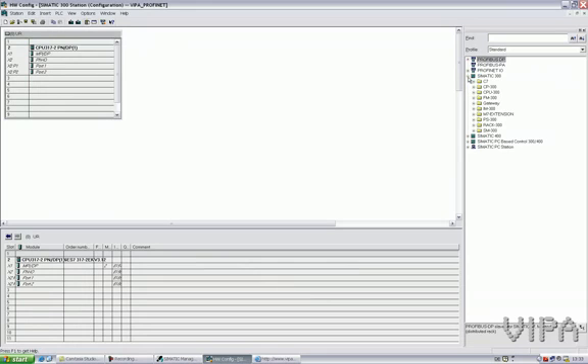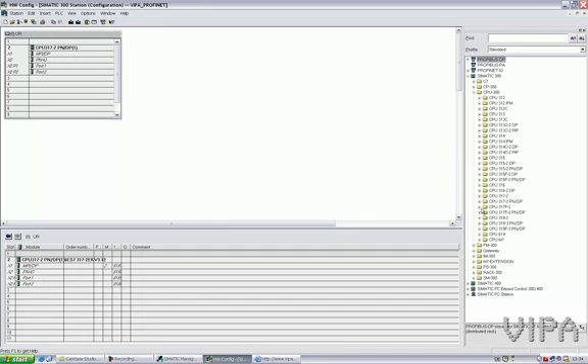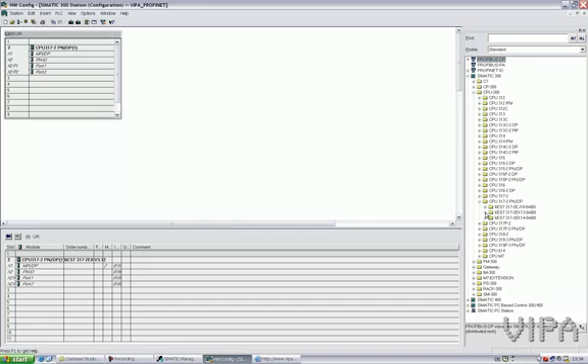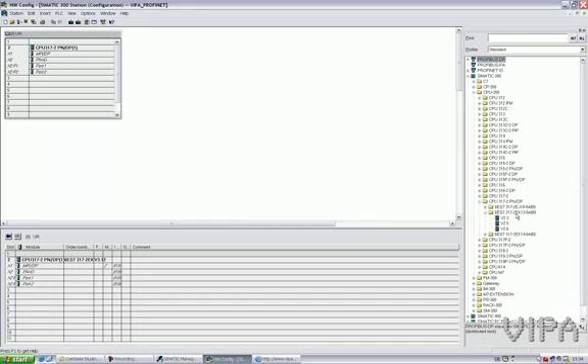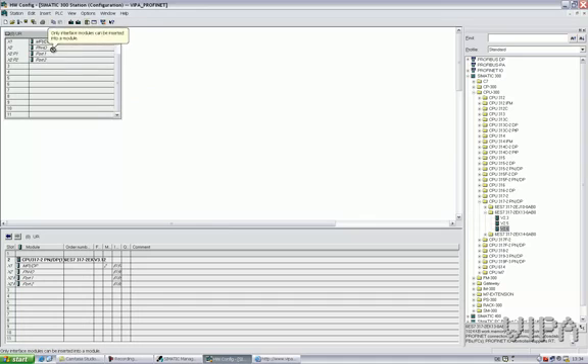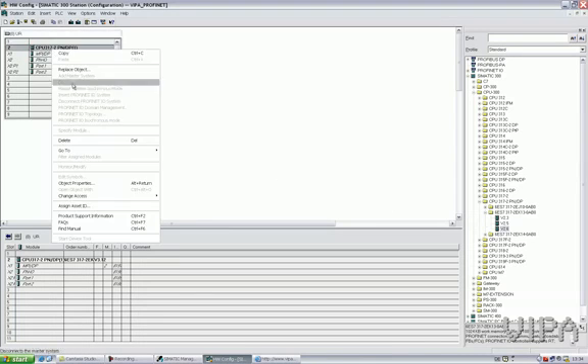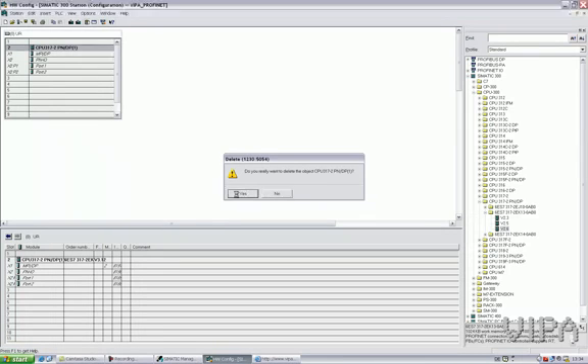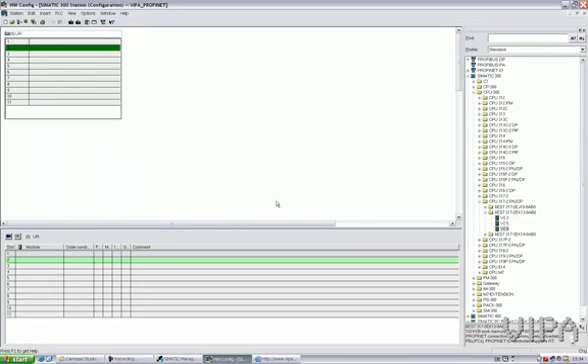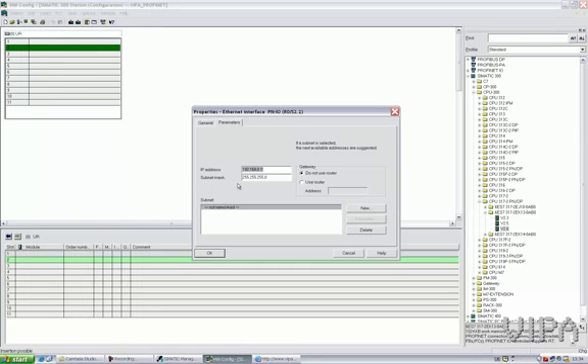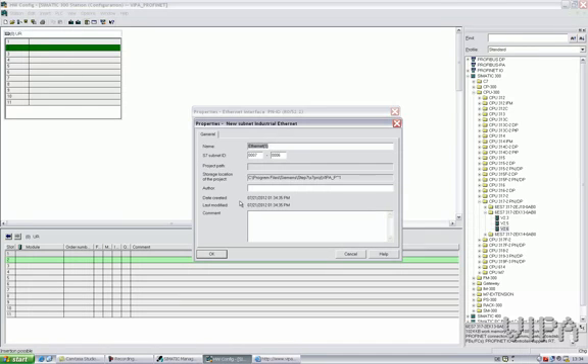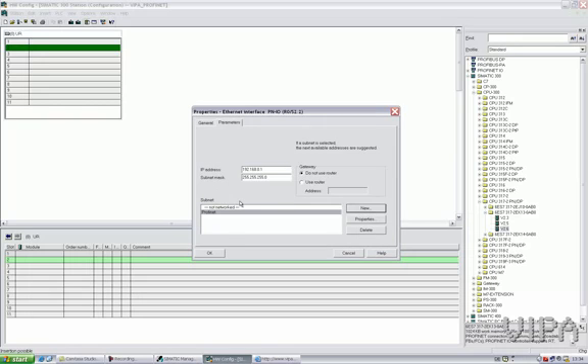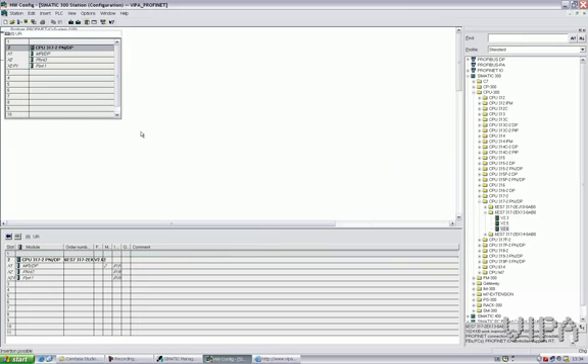So, in the hardware catalog of Simatic Manager, I go to the CPU 317 PN-2EK13 version 2.6. Okay, I'll first delete this one. Delete. Yes. And no, I do not want to delete my OB1. IP address is fine for me, 192.168.0.1. I'll create a new network. This is my Profinet network. Okay.